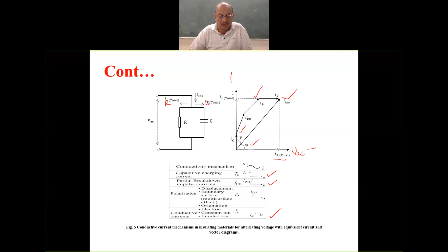Now, delta has been chosen for this angle here, which is 90 minus the power factor angle. In fact, delta is very small, unlike what is shown here. It has been shown as something like 45 degrees. It is wrong, but just for clarification, it is shown here like that. But the delta angle is very, very small, and tan of delta will give you the component of the total insulation current. I insulation multiplied by tan of delta will give you the component of the current in phase with the applied voltage here.